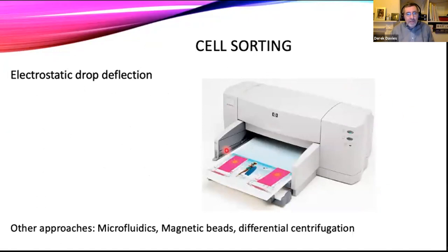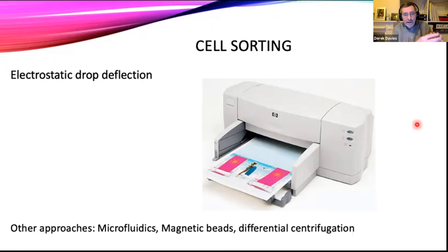The way most of the sorters we're likely to come across in the flow cytometry world work is very much the same as the way an inkjet printer works. You quite often don't need to know how an inkjet printer works — you press print on your computer, you walk to the printer and there's your page. But it works by the principle of electrostatic drop deflection: we form small droplets of ink, we give them a charge, and they pass through an electrical field and are moved to whichever area of the paper your red, blue, green, or black ink goes.